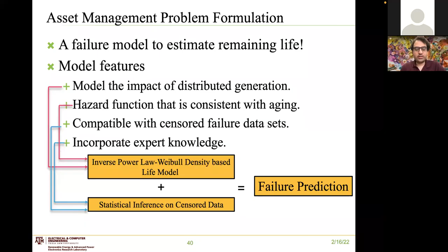Utilities have been operating these devices for decades now, and they have accumulated a lot of knowledge about the failure of these devices. So what we do to address these conditions is propose the use of inverse power law combined with a Weibull density model. To make sure our model is compatible with the data available and can incorporate expert knowledge, we propose an inference scheme that works with censored data. When we combine the two, we end up with a failure prediction model that learns based on past historical data and can make predictions about failures that might happen in the group of transformers that is still surviving.